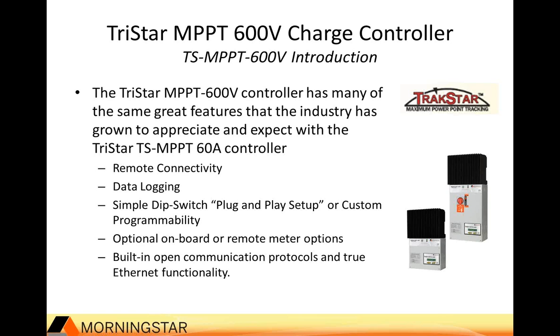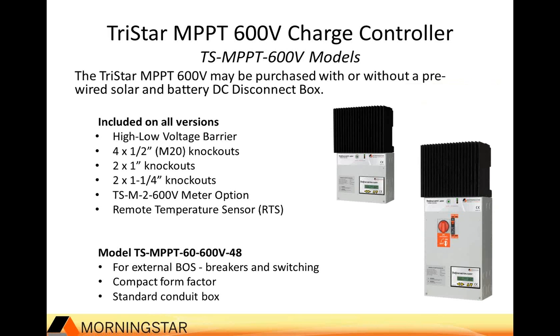Okay, so the TriStar meter family has a new feature, which is the 600-volt version, and that will give you additional information pertaining to this product. Like the other controllers, it's able to be used with up to 4 units in parallel, so you can aggregate the data from all 4 controllers onto one meter display. And lastly, we also offer the built-in communication protocols and true Ethernet functionality that we've offered on the TriStar MPPT 150. So that's all included on these units as well.